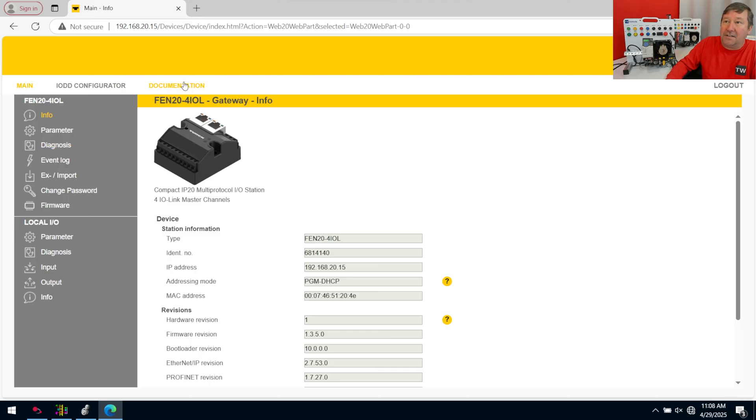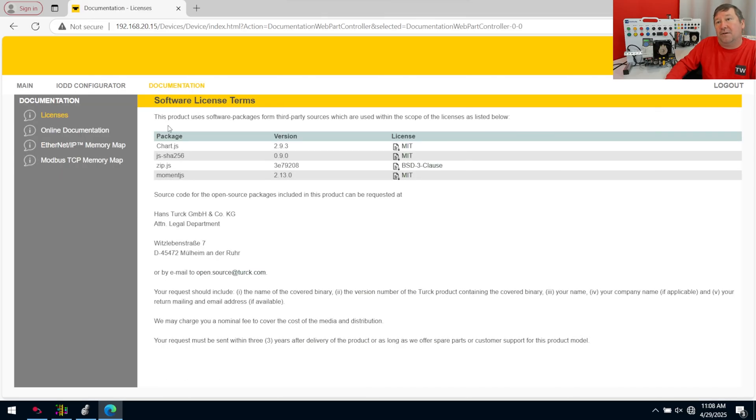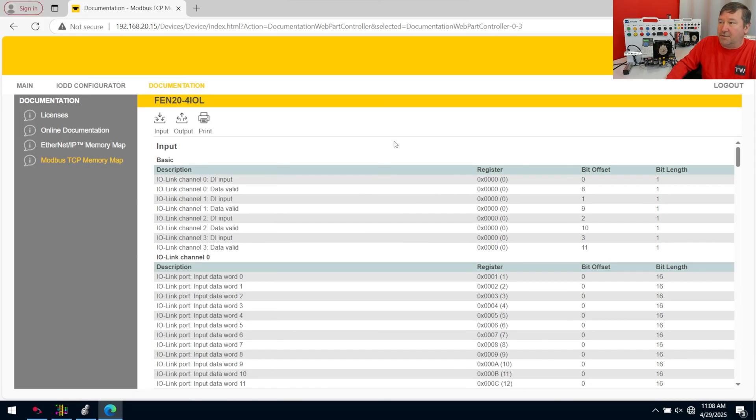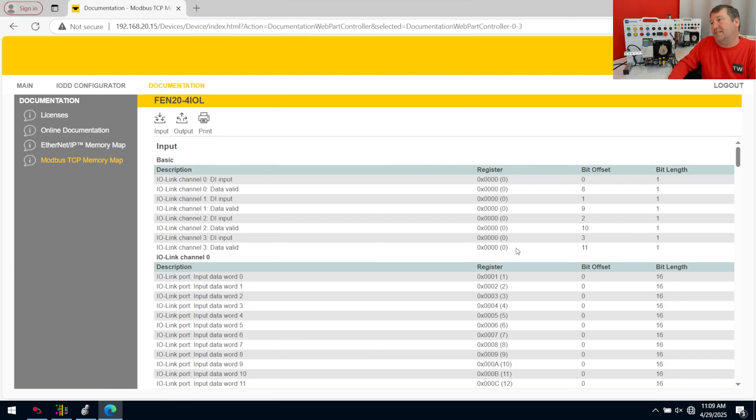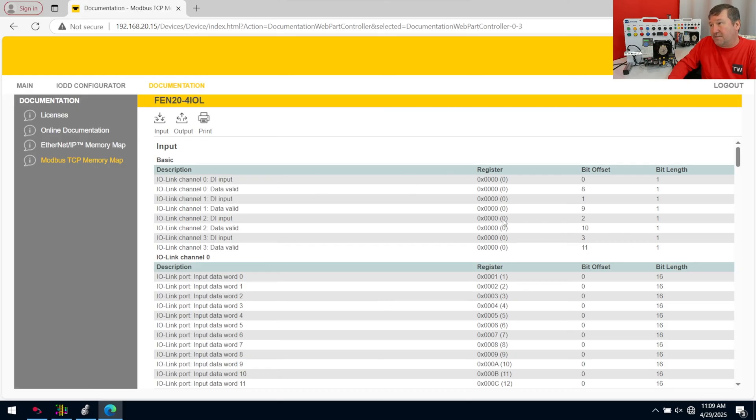And then we're going to go to the documentation tab up here. And then Modbus TCP memory map. And this tells us where the actual data structure is. Now, here is always the trick to Modbus. In fact, this may be the most difficult trick. And even when it's documented half the time, it doesn't make sense. Is did they start at zero? Or did they start at one? So, Turk, their numbering is starting at zero. So register zero is their first one.